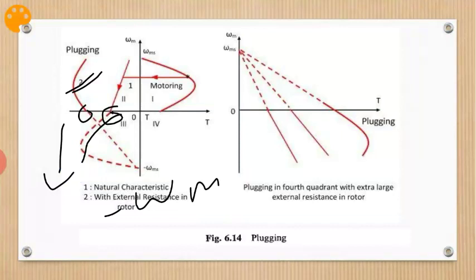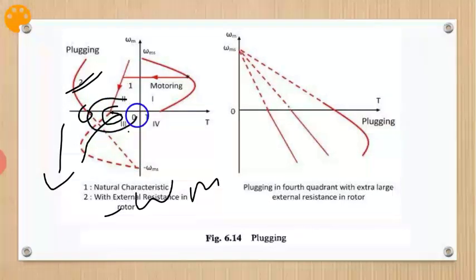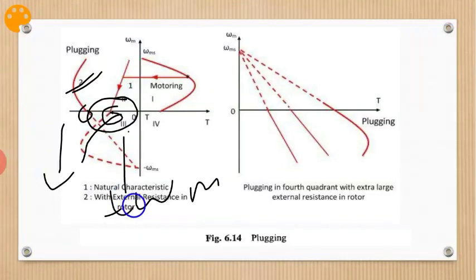This type of braking is usually suitable for reversing the motor. Such braking is employed for reversing the motor, because as soon as it goes to zero speed, it is driven in the reverse direction. As the motor is already connected for operation in the reverse direction, torque is not zero at zero or any other speed. The motor smoothly decelerates and then accelerates in the reverse direction.